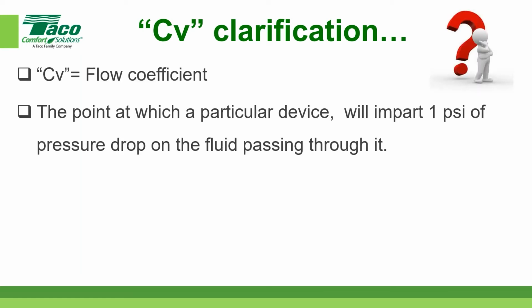I think a CV clarification, I'm just going to wrap this up in the next 5 minutes, just reminding you what the CV is all about. CV stands for the flow coefficient, or it's a shortened abbreviation, not really an abbreviation, just CV. Some people have tried to say coefficient of velocity or something like that. I've never found anything other than what we call the flow coefficient. Coefficient meaning just the number of that particular device when it was tested.